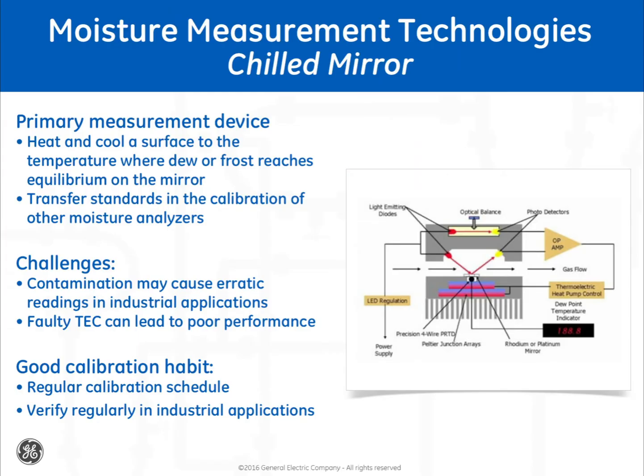Chilled mirror moisture analyzers are a primary measurement device, as they measure the temperature at which dew or frost reach equilibrium on the reflective surface. Given that these devices are often used as reference standards for the calibration of other devices, it is best practice that these be calibrated on a fixed schedule. This is typically accomplished at the manufacturer's facility or at accredited calibration labs.